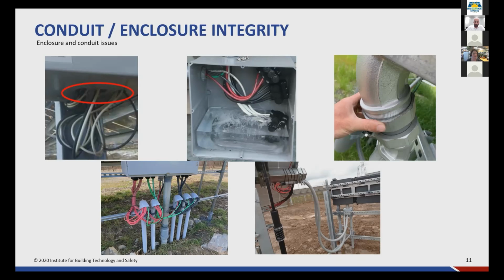Frost sleeves on conduit that goes underground are a big one, so that when the ground moves as it freezes, the conduit can move with it instead of staying in place and cracking and breaking. Or just general conduit management—we've got a picture of conduit held up with plastic wire ties, dangling loosely where it goes to the next enclosure. That will not last the 25-year life of this system, so that needs to be dealt with.